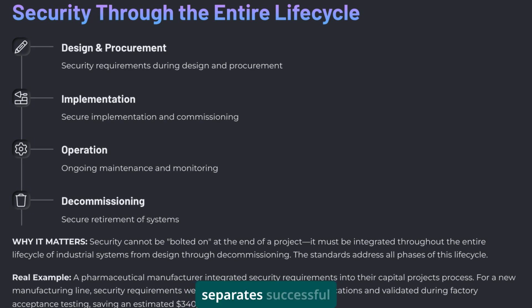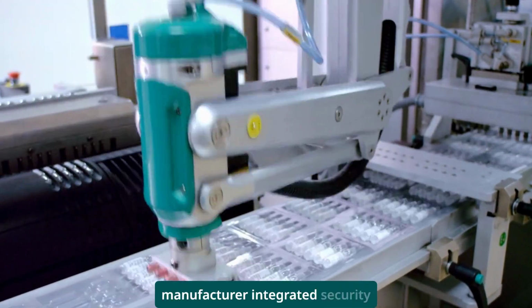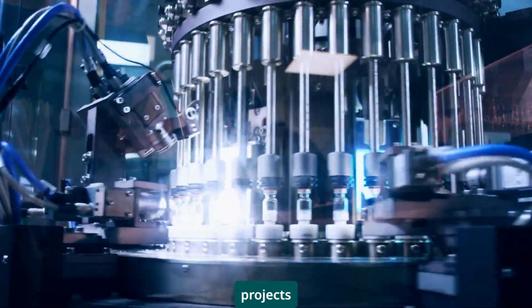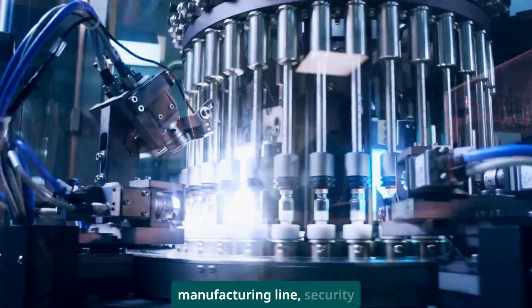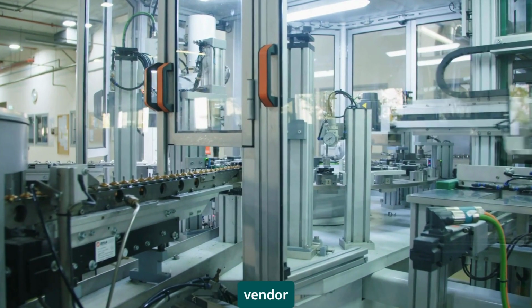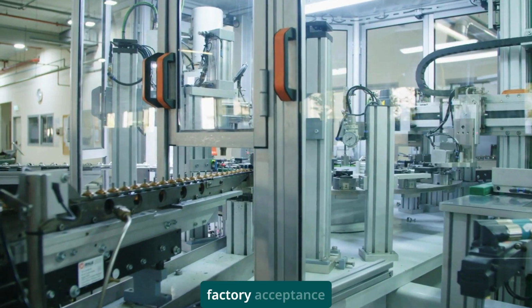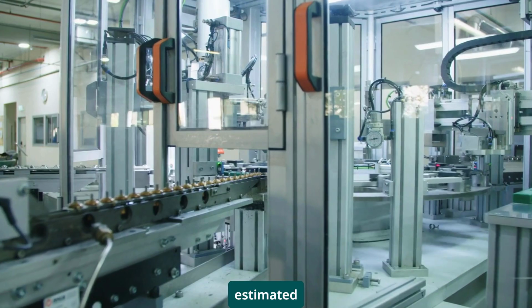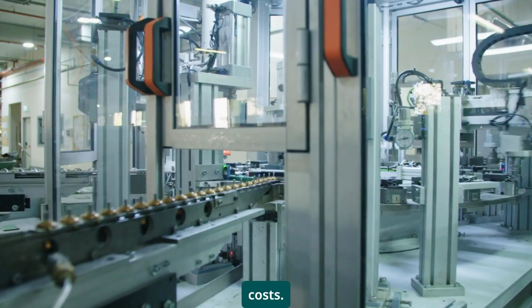Here's something that separates successful implementations from failed ones. Integrating security throughout the entire system lifecycle. Security can't be bolted on at the end of a project. It must be considered during design and procurement, implemented during commissioning, maintained during operation, and properly handled during decommissioning. A pharmaceutical manufacturer integrated security requirements into their capital projects process. For a new manufacturing line, security requirements were included in vendor specifications and validated during factory acceptance testing, saving an estimated $340,000 in retrofit costs.